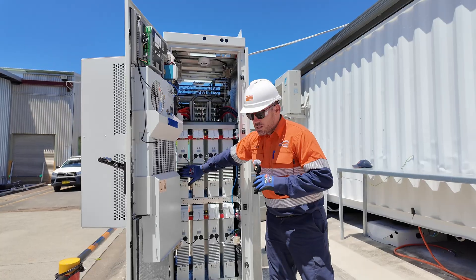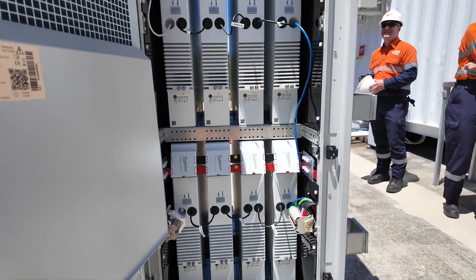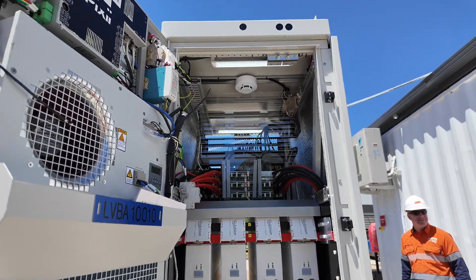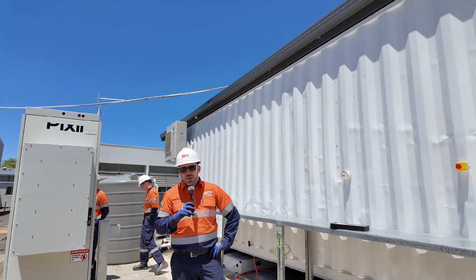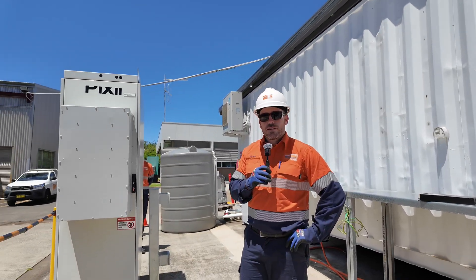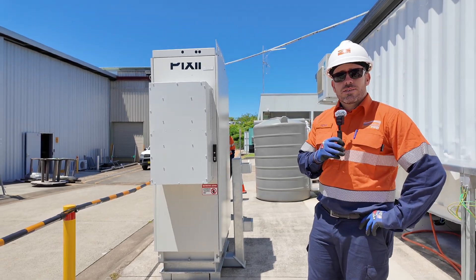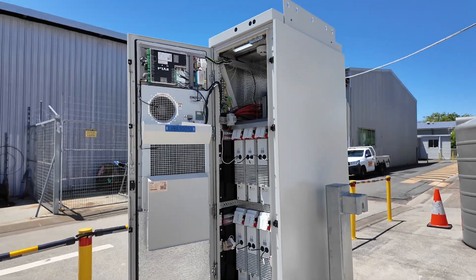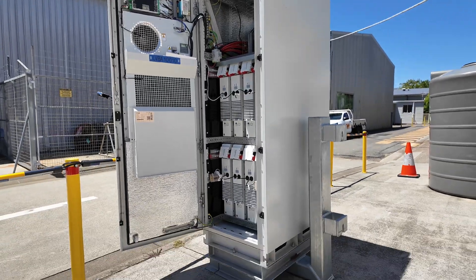We've also got a second battery type called EcoJewel that's also pole top based — they're out of Brisbane as well. These are separate batteries. So these are your actual cells, and each of them have their own protection, so they're monitored and they're safe. They work together to give us that overall capacity. You can see behind me here is Essential Energy's Quality Assurance Lab. Every new asset that we bring into the business, we put through significant testing so that we understand how it operates, any safety implications around that asset and how we best manage it. These batteries are operationally tested and their safety features are tested so that we're confident that what we're putting out there is safe for the public.